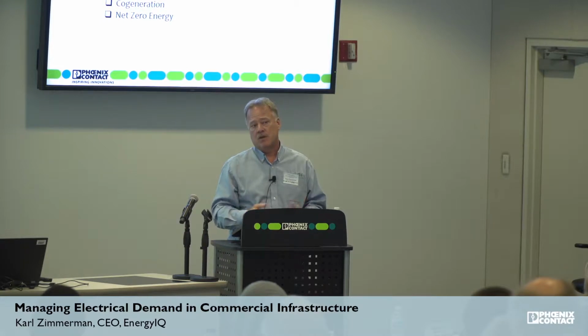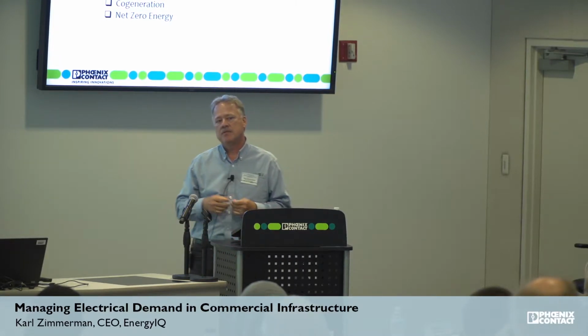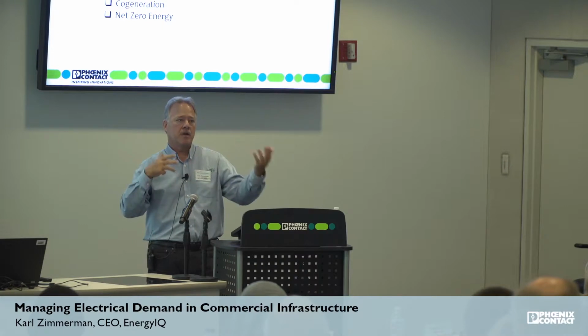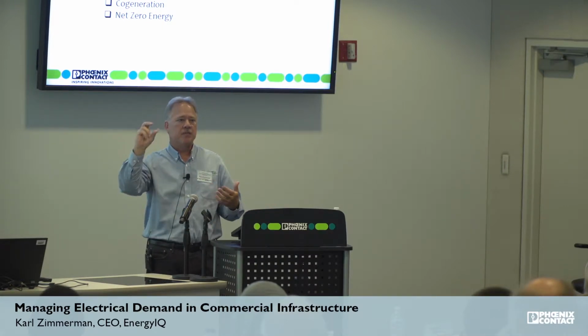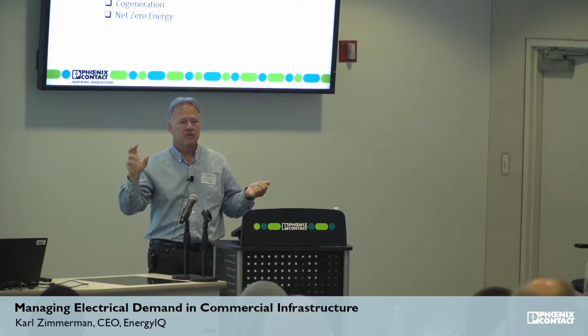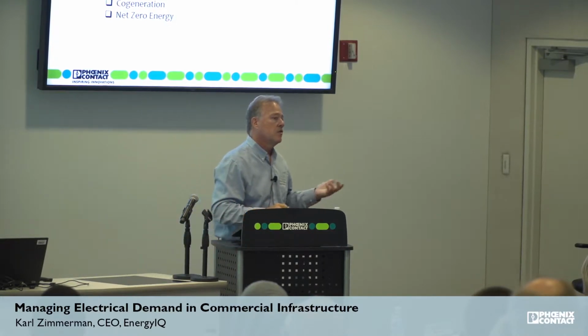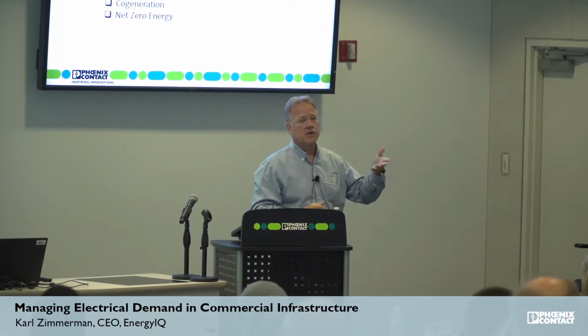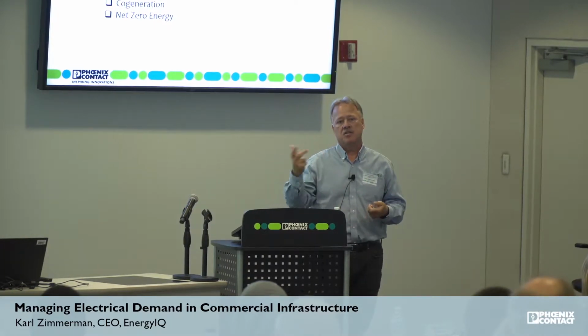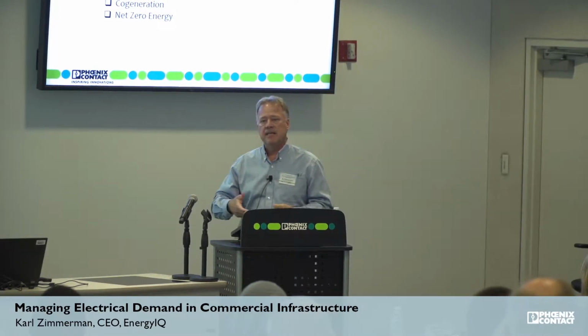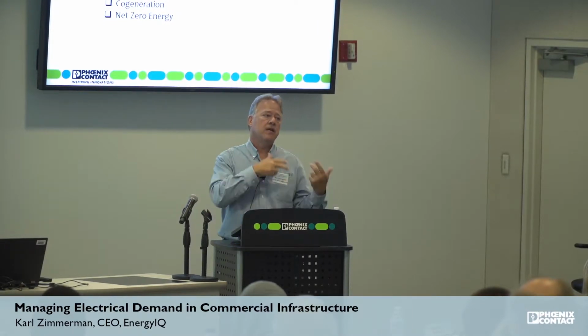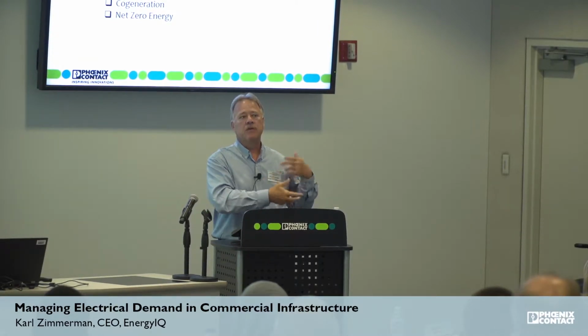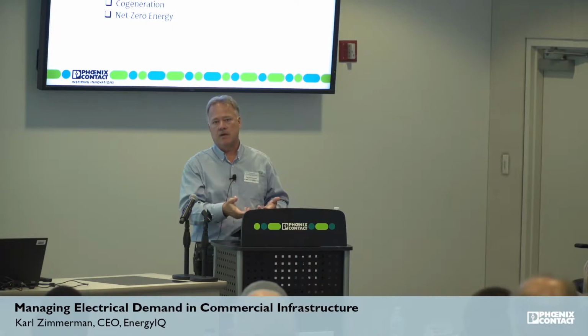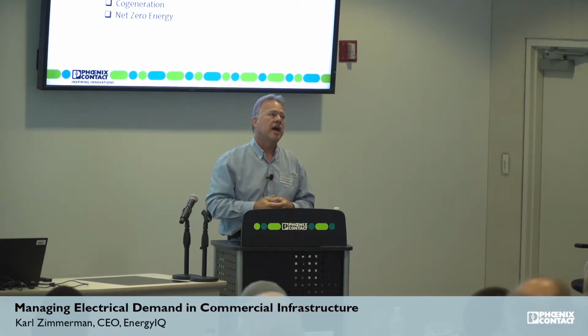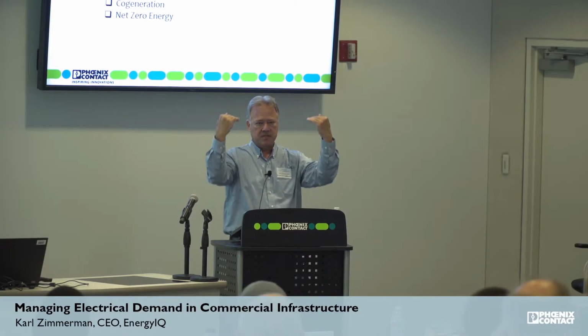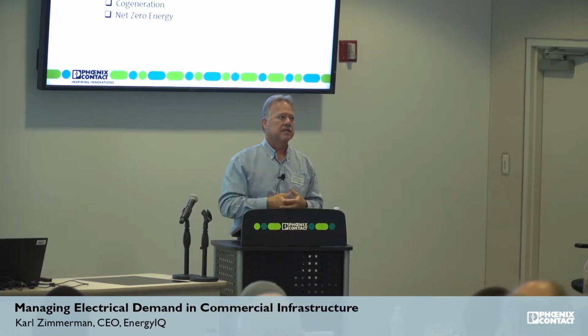Another one is something called cogeneration. Right now, if I were to have an electric chiller producing chilled water to run this building, my efficiency would be maybe 40% or something like that of use of that energy. Where we can use cogeneration, which is what this facility does, is you take natural gas, you use a turbine, you produce electricity, and then you take that waste heat and run it into an absorption chiller that will then use that waste heat to create the chilled water. So now your efficiencies are much higher. So that's another way to reduce the demand profile of, say, a building like this.